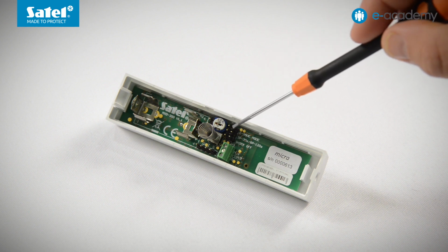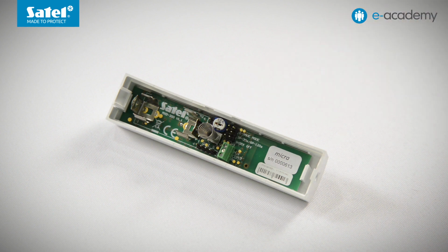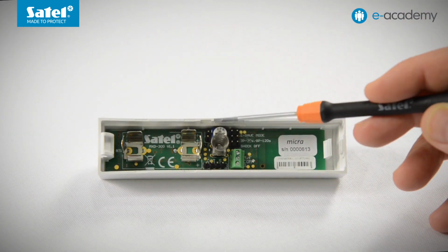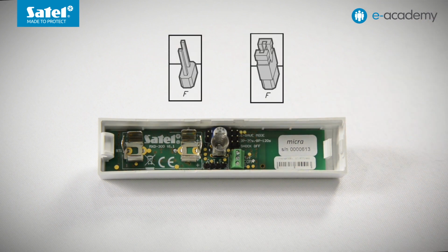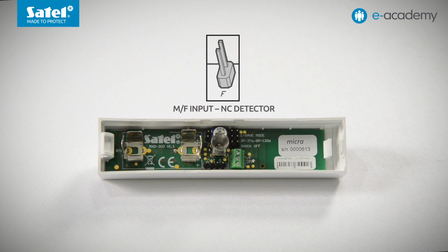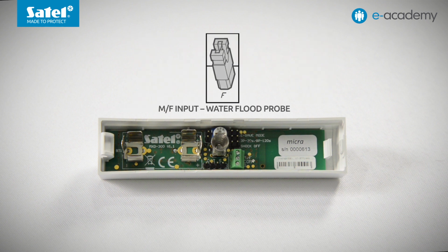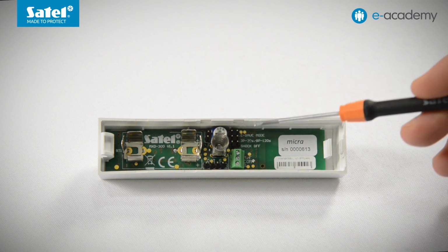Here, 3 groups of pins for detector configuration are located. The first pair is used to define which device is to be handled by the MF input. When there is no jumper on the pins, this input will handle a NC-type detector, e.g. a wired magnetic contact. And when the jumper is placed over the pins, the MF input is ready to work with the flood probe. Let's take a look to the right.